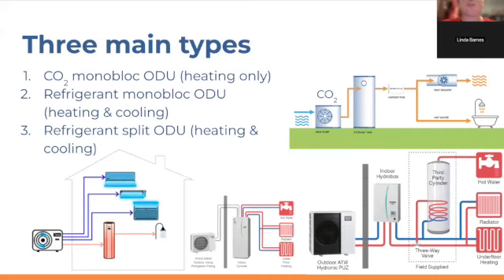Now, you can get some of them, and then you might be able to get an exception from your authority having jurisdiction to install one under the auspice of, like, pilot testing, a pilot program, that type of allowance. But it is different in Europe. The regulations on propane and A3 highly flammable refrigerants are a little bit looser, and so there are places in Europe where you can install a refrigerant monoblock outdoor unit that uses propane, and have it fully approved by the authority having jurisdiction.